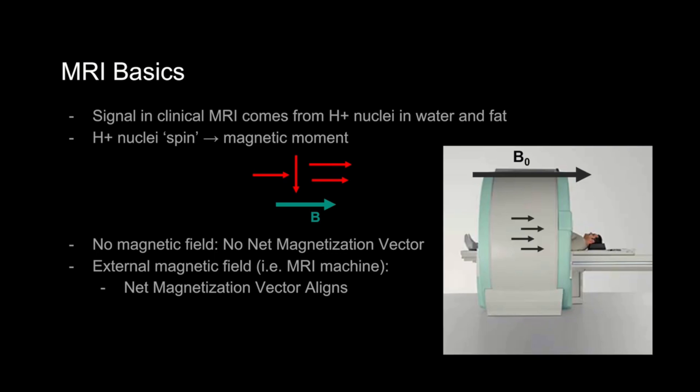Let's look at an MRI machine. So a big part of this MRI machine acts essentially as a big magnetic field that is aligned down the bore of the magnet, and that's marked here as B0. The main magnetic field is down the bore of the magnet, which is also called the z-axis or z-axis. The strength of the magnetic field in clinical MRI these days is most commonly 1.5 or 3 tesla, and this diagram shows these magnetic moments of the individual hydrogen molecules aligning with this field.